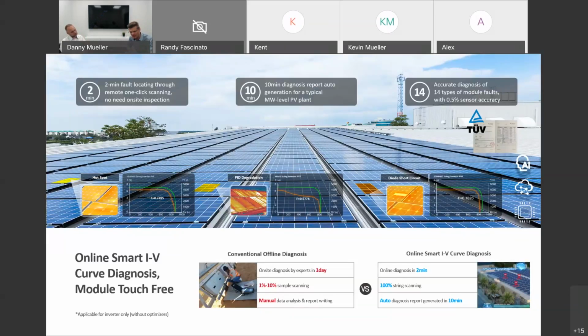It's all about how the data is provided to you, and Huawei, again, similar to the Inverter Patrol, has a feature where the IV Curve Tracing and the reporting of the IV Curve Tracing focuses on the deviation from the norm. So you can, of course, go through 1,000 strings and 1,000 diagrams yourself and do the analysis. That's certainly possible, and you have the data available. But it's really of value that you focus on the strings where the inverter system and the automatic analysis told you there's something wrong compared to the other systems, or something out of the ordinary. So you can focus on the 10 strings of your portfolio which are a little bit outside of the ordinary. Next.